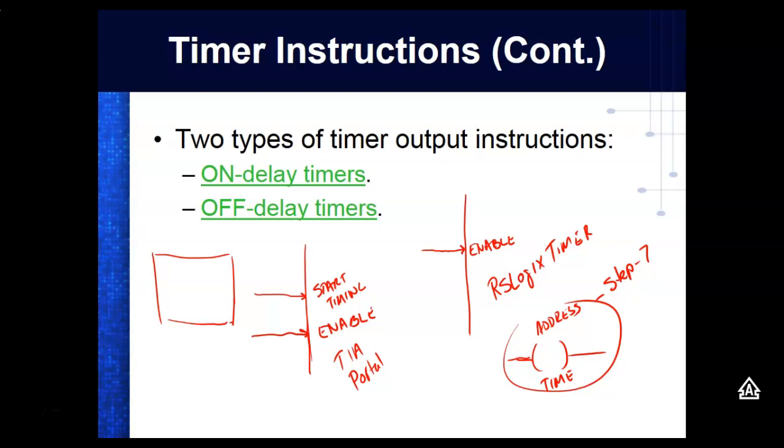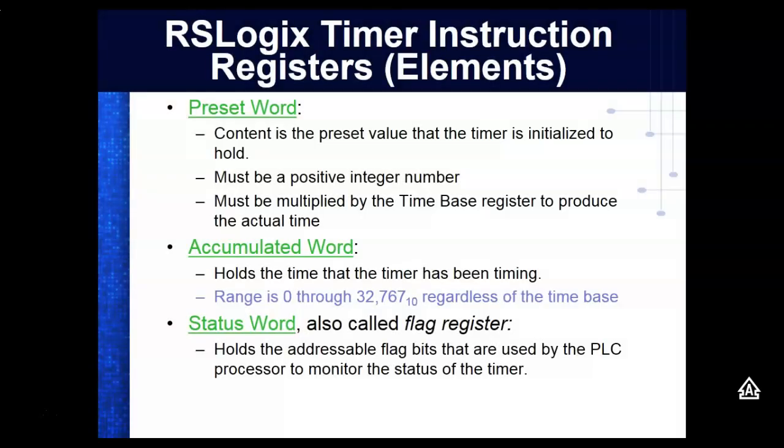Off delay timers, on delay timers, are y'all okay on those? So an on delay timer starts timing when the rung becomes true. An off delay timer starts timing when the rung becomes false, right? And of course, we've got the block type.